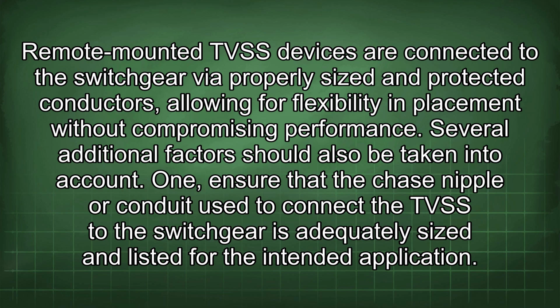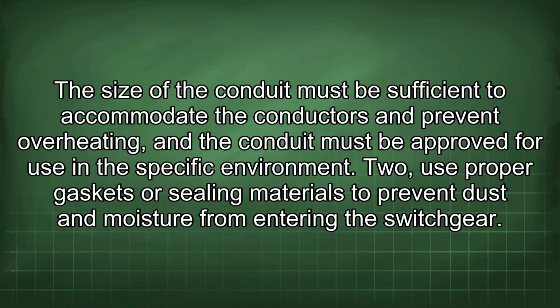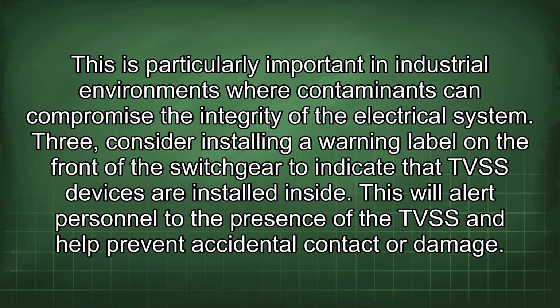1. Ensure that the chase nipple or conduit used to connect the TVSS to the switchgear is adequately sized and listed for the intended application. The size of the conduit must be sufficient to accommodate the conductors and prevent overheating, and the conduit must be approved for use in the specific environment. 2. Use proper gaskets or sealing materials to prevent dust and moisture from entering the switchgear. This is particularly important in industrial environments where contaminants can compromise the integrity of the electrical system.